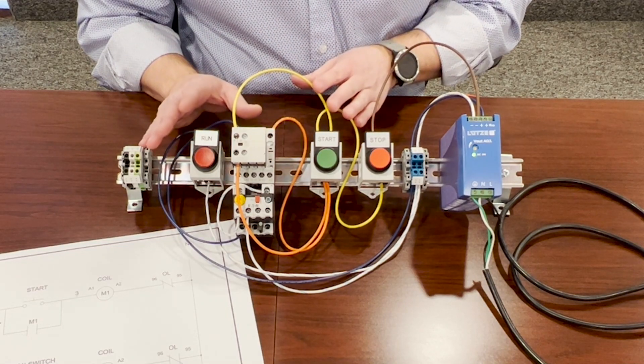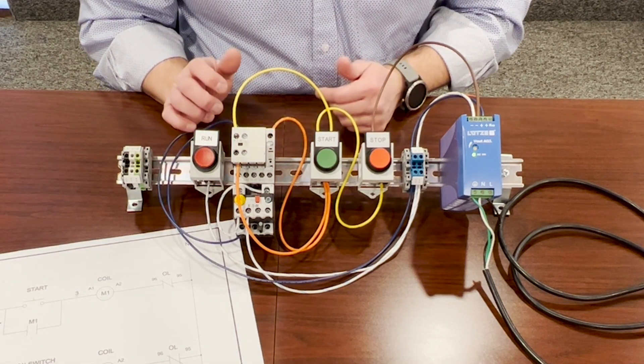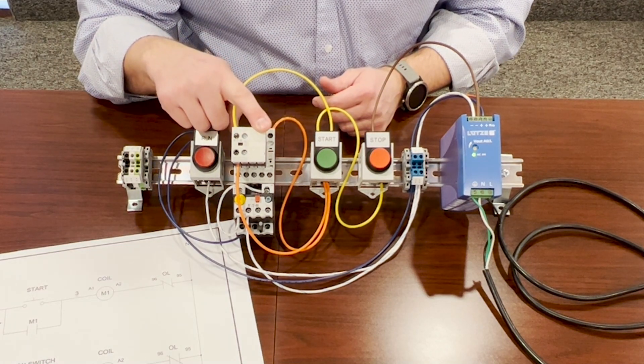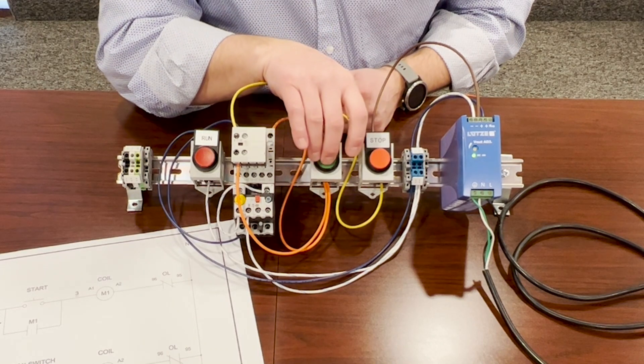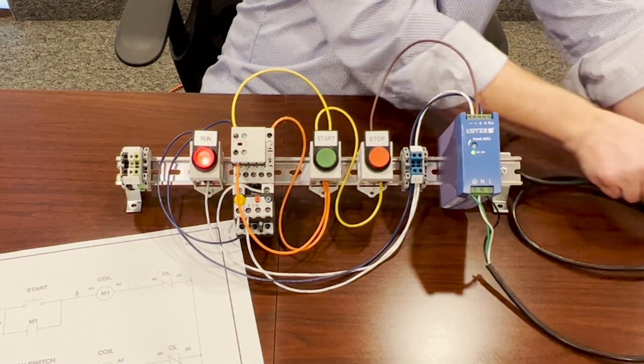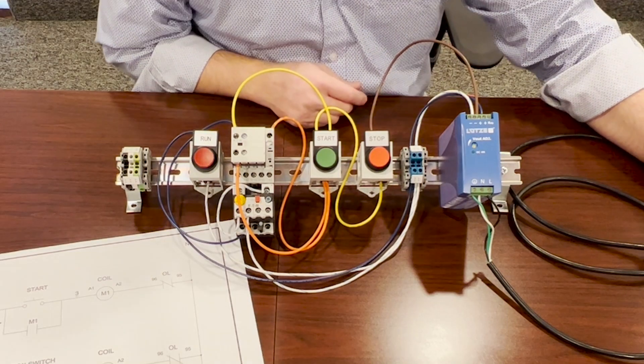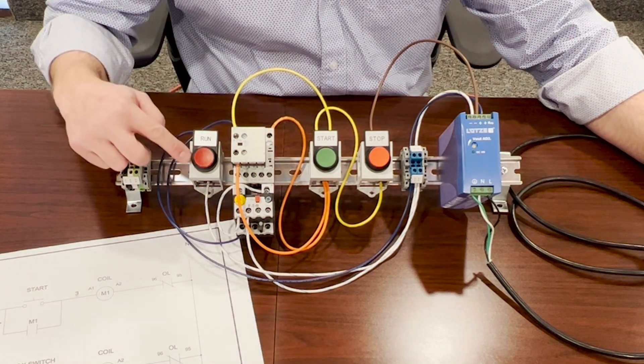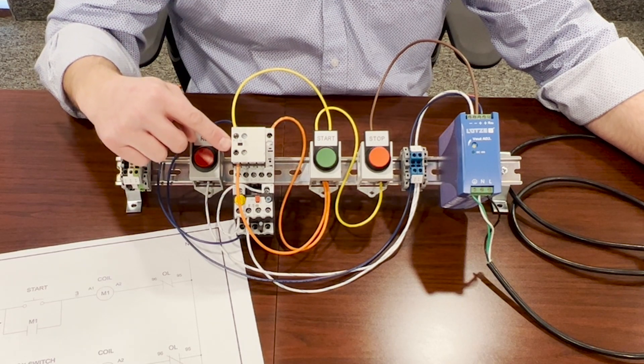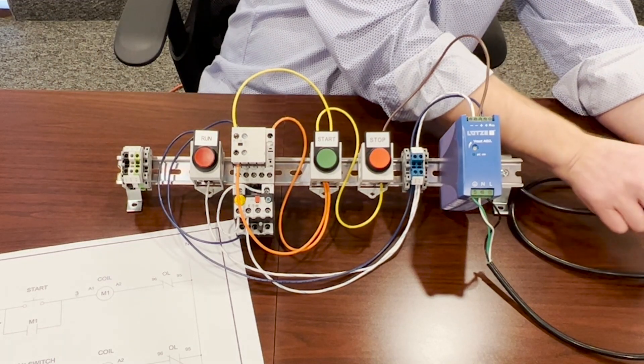The beauty about this circuit is in case of a power outage, this will not come back on automatically. So if we start this back up and then we're going to unplug or disconnect, just like if the power was removed, and you can see our light turned off. That means that this contact is open, because the motor starter is de-energized.